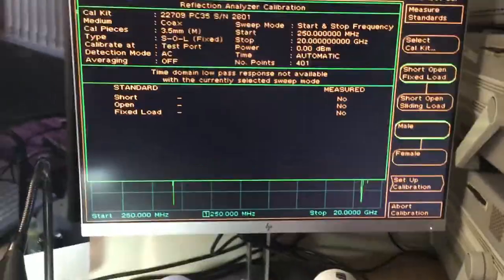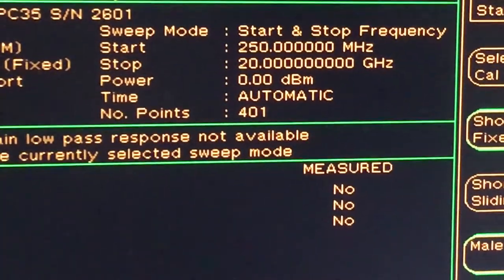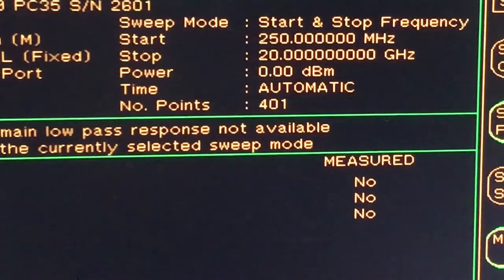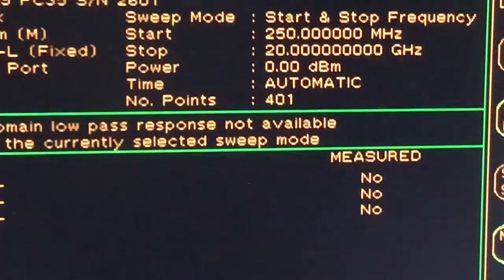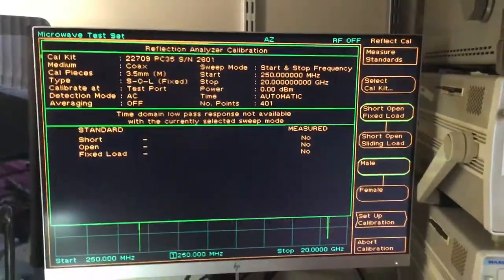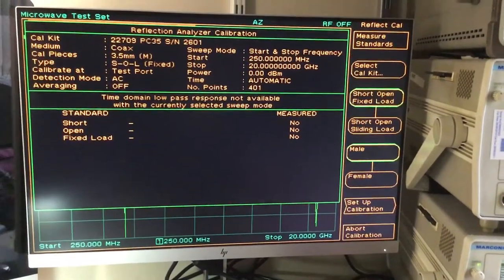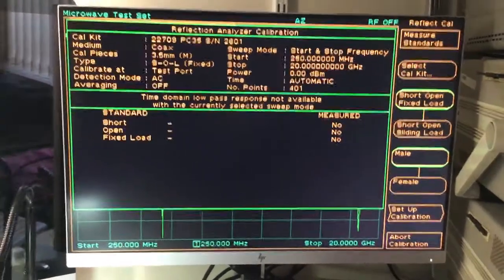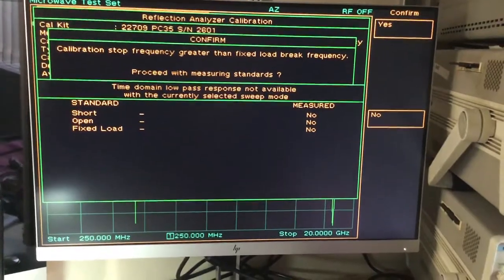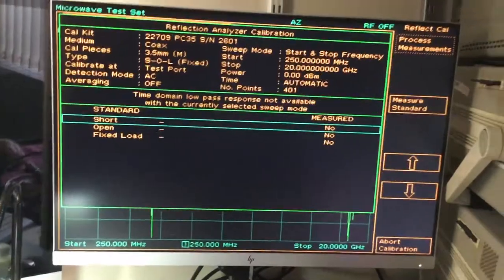So we're starting at 250 megahertz, and we're stopping at 20 gigahertz. We've got a source power of 0 dBm, and we're using 401 calibration points as part of that measurement. So how we do that now is we select measure standards, which is again in the top right. We've obviously wished to confirm that we wish to do this, so that's yes again.